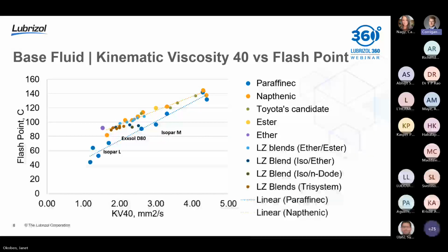And so if we look at this graph here, you can really see two distinct trend lines. One for the pure hydrocarbon-based fluids, so things that are just carbon and hydrogen, and then one a little bit above that. And those types of fluids are typically a little bit more polar. They contain oxygen. So rather than pure hydrocarbons, they might have some ester in them as well. And looking at this chart, you see, okay, well, if we go to an ester system, we can maintain that low viscosity and also boost our flash point. So that's really attractive from a performance and a safety perspective.